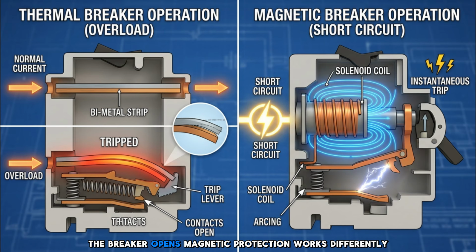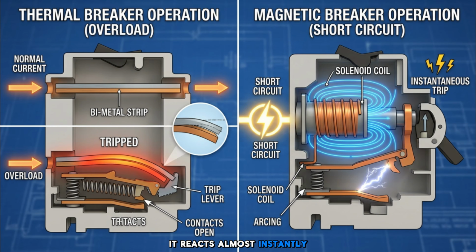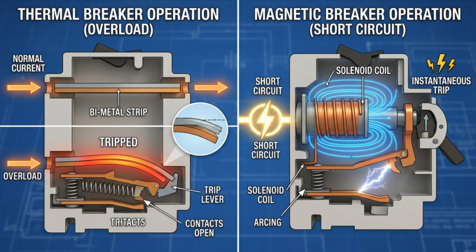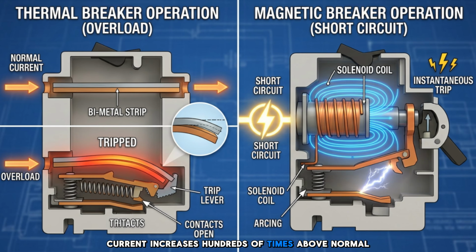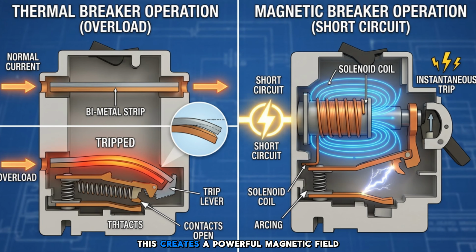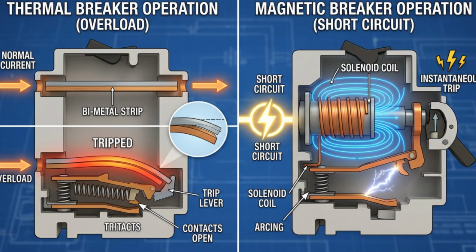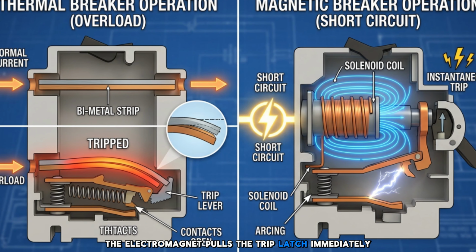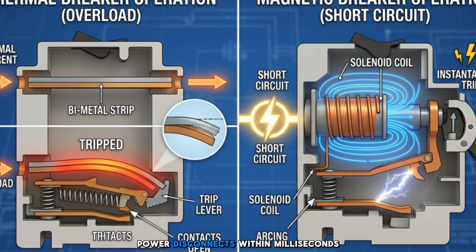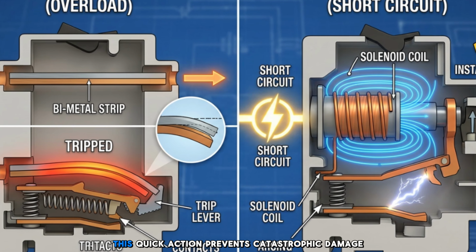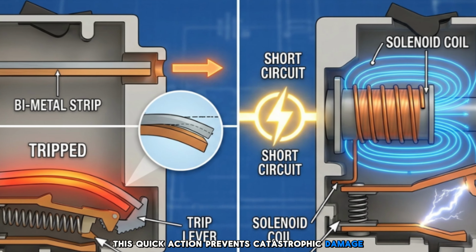The breaker opens. Magnetic protection works differently. It reacts almost instantly. During a short circuit, current increases hundreds of times above normal. This creates a powerful magnetic field. The electromagnet pulls the trip latch immediately. Power disconnects within milliseconds. This quick action prevents catastrophic damage.